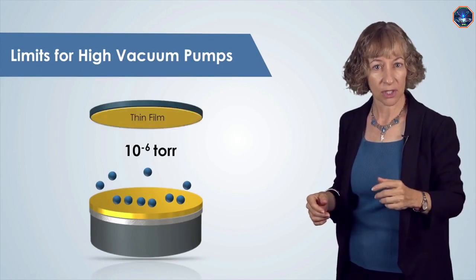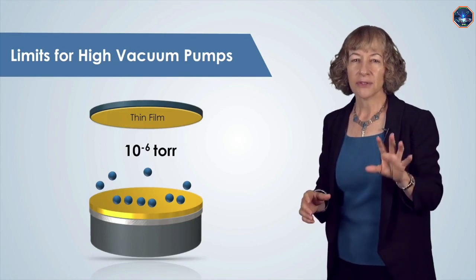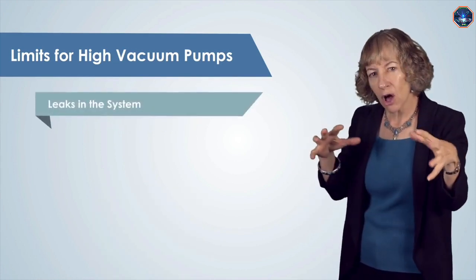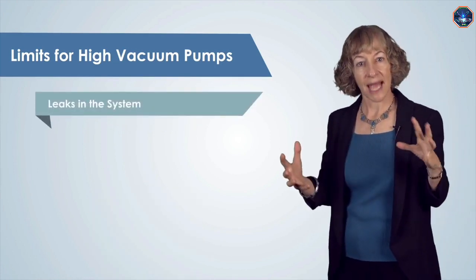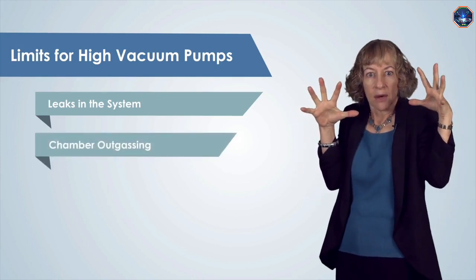High vacuum pumps can achieve 10 to the minus 6 torr for depositions, and they can achieve even lower pressures than that, but they're typically limited by small leaks in the system or in gaskets, or if the system out-gases, which means there are air molecules of trapped gas in the system—they tend to come off the chamber walls as the pressure decreases.